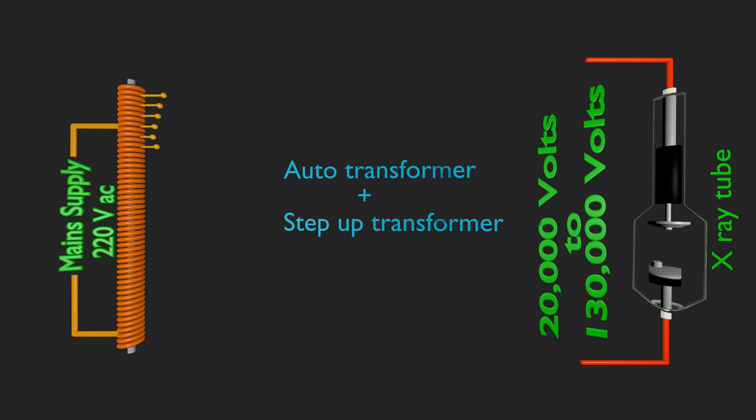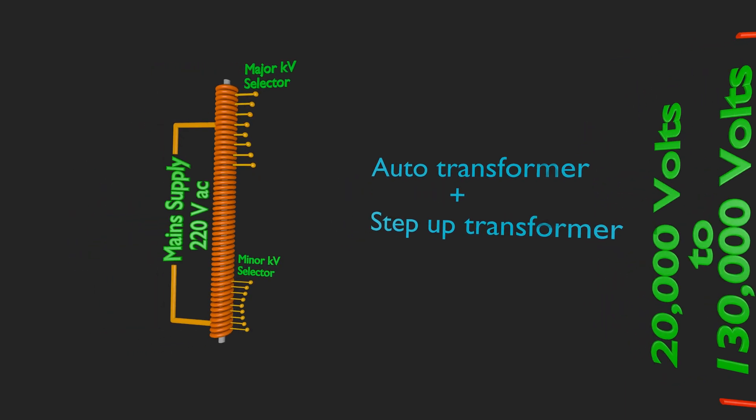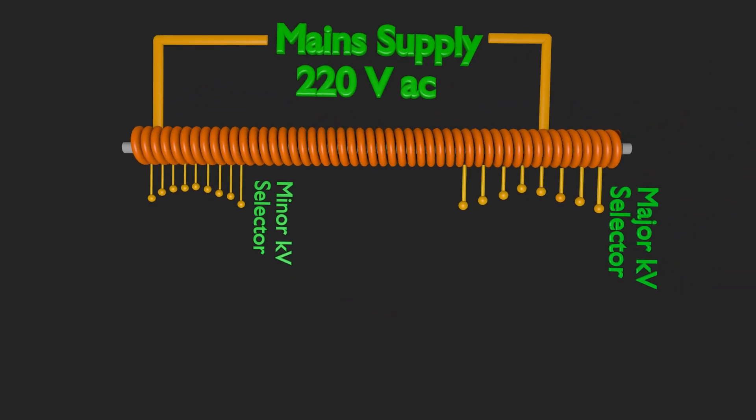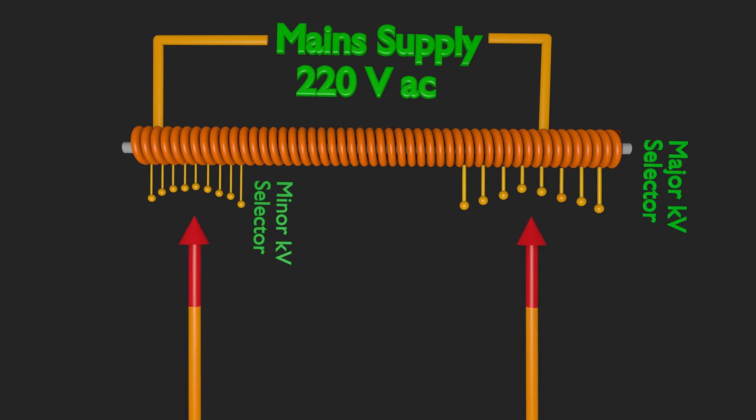But the secondary section have different taping points to have variable turns. As the taping point changes, the ratio of turns in secondary to primary changes.